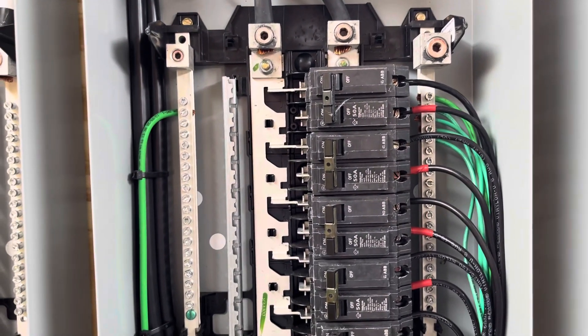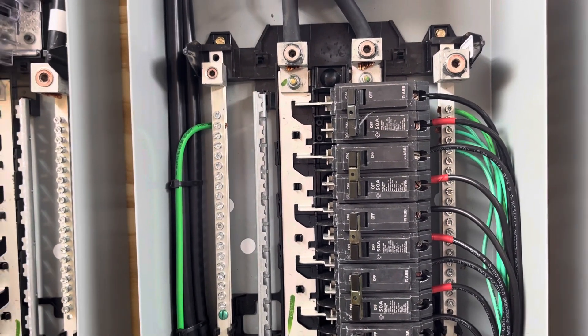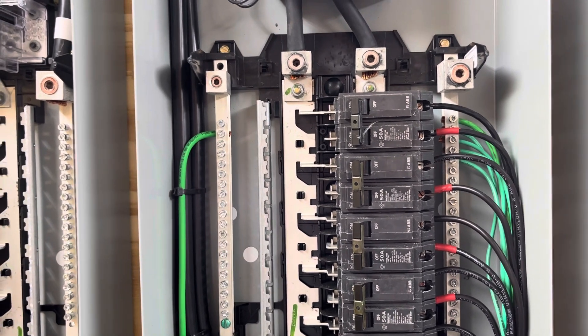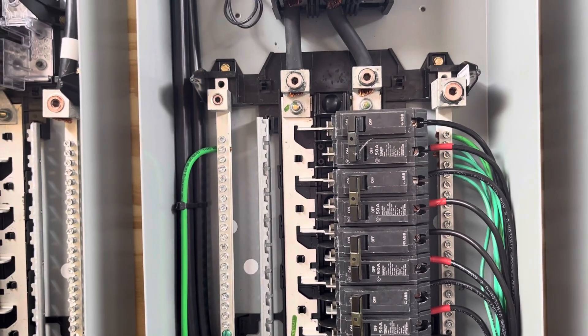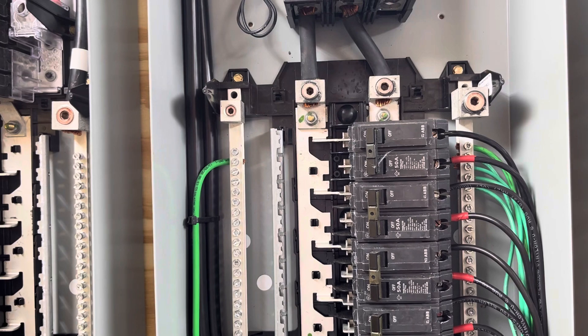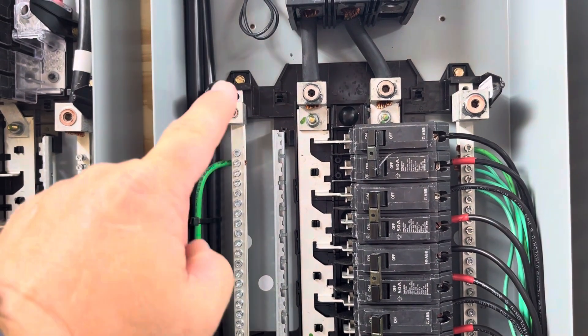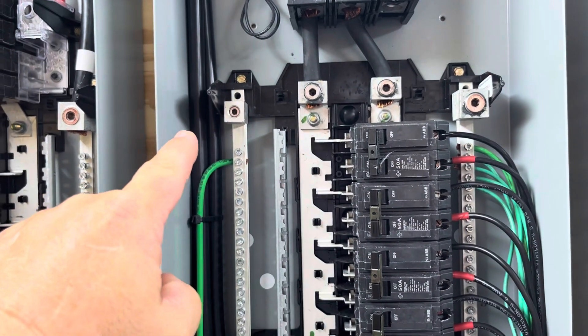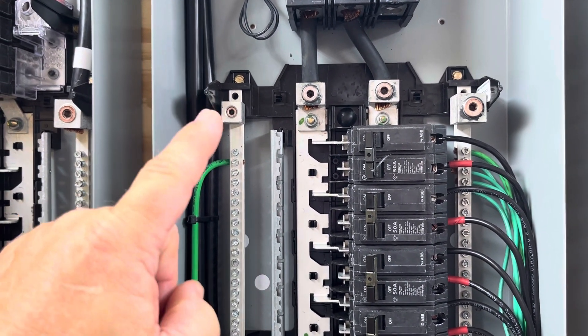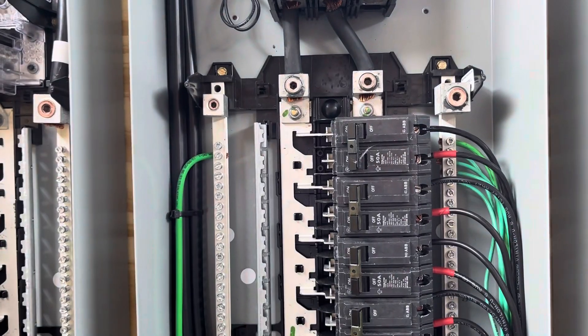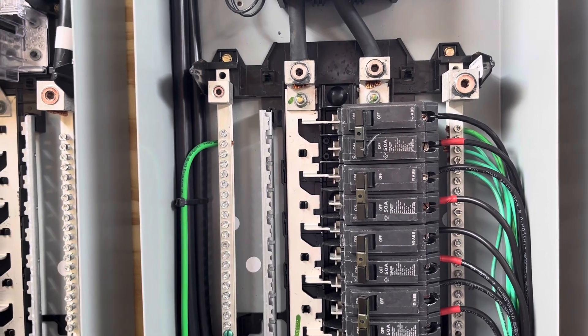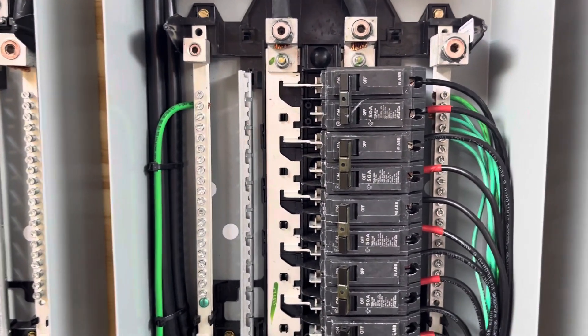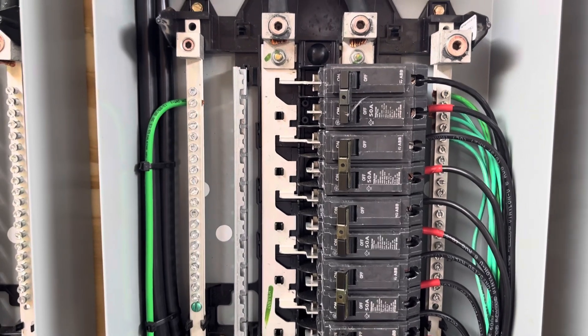Now, when it's in inverter mode, as I mentioned, L1, L2 have no reference to ground, because the inverter is strictly putting out 240 volts. And as I've shown in another video, when I measured the voltage from L1 to ground, I think it was like 99 volts. L2 to ground, it was like 148 volts, which is not surprising because the whole thing is floating when it's in inverter mode.